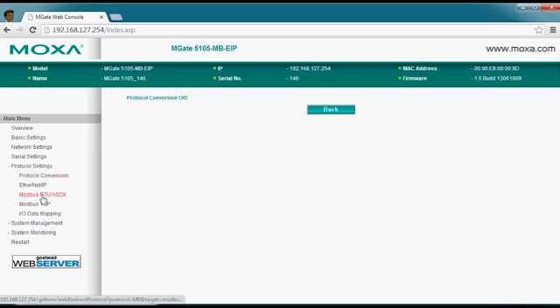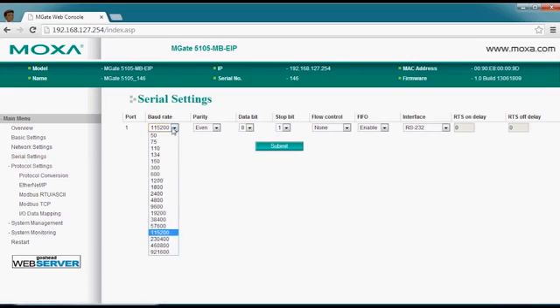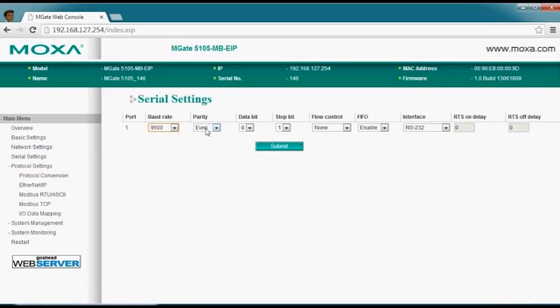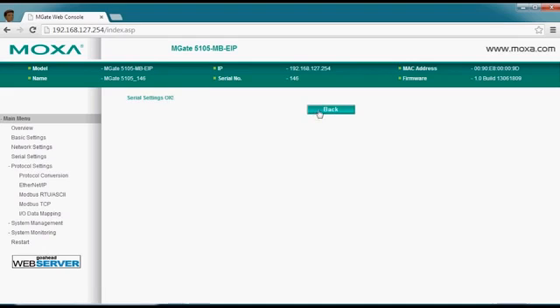Since we've selected a serial connection for the VFD, we need to go in and set the serial port settings. In this case, we're going to select 9600 bits per second, keep even parity, eight data bits, one stop bit. We also want to change the interface to RS-485. So let's go ahead and make those changes active.